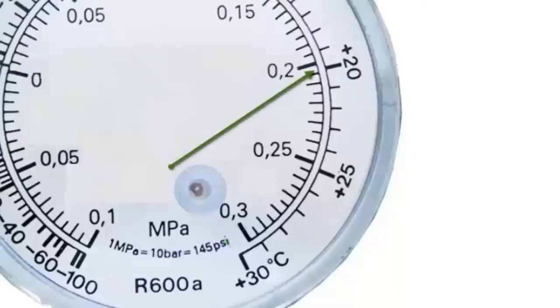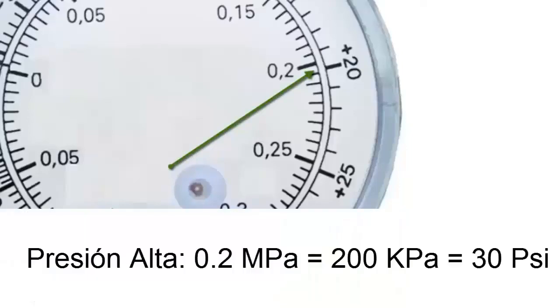If we want to know the pressure that the equipment should have being turned off, we are going to search the manometer for the value of the ambient temperature. That is, we place the needle at 20 degrees Celsius, and thus we can read the pressure value.